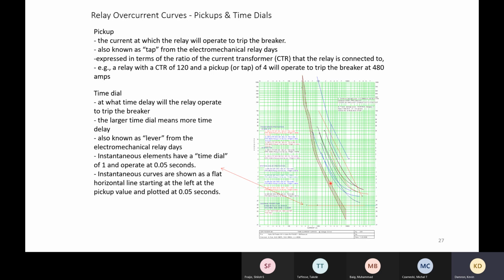If for some reason a fuse failed or it didn't interrupt the fault, we would go up and start running into the protective curves. In this case, we've got a fuse, we've got the station breaker, and then the transformer relays. So the way you read these is, you just follow them straight up. Pick what your fault current is, follow it up, and it will tell you exactly how the devices operate.